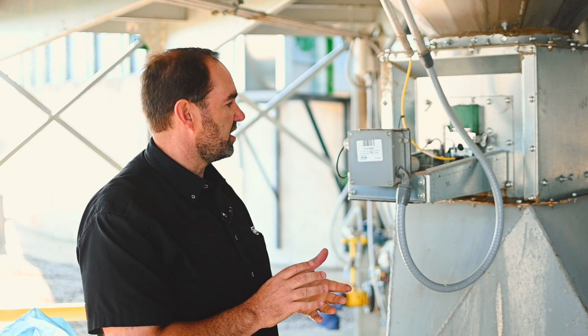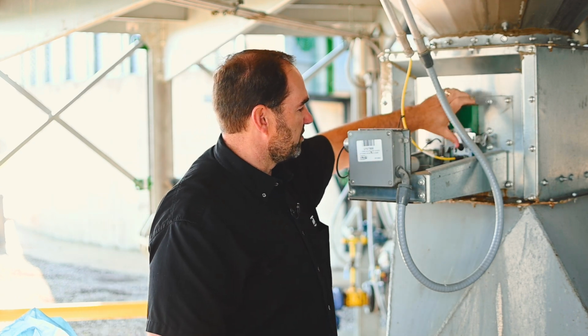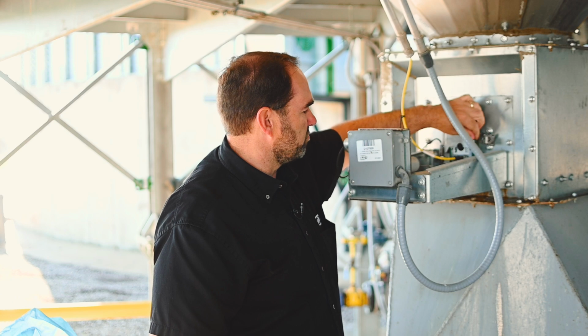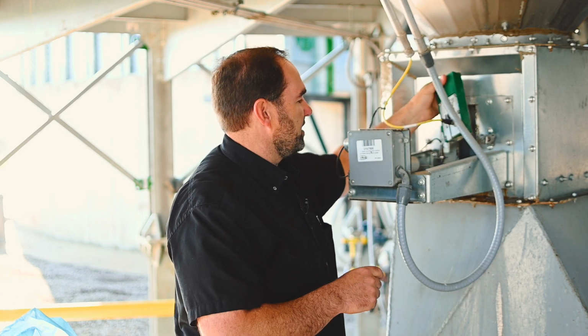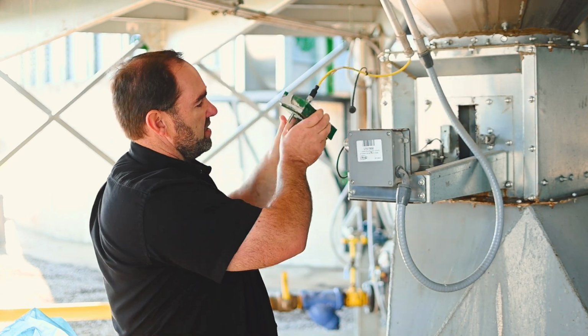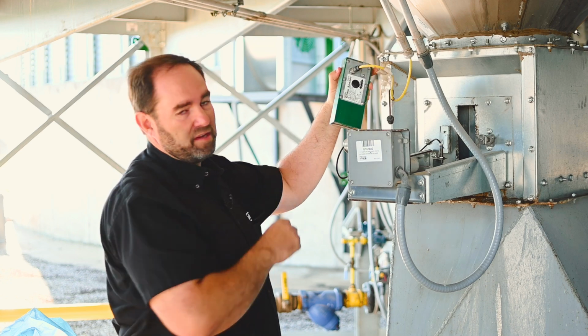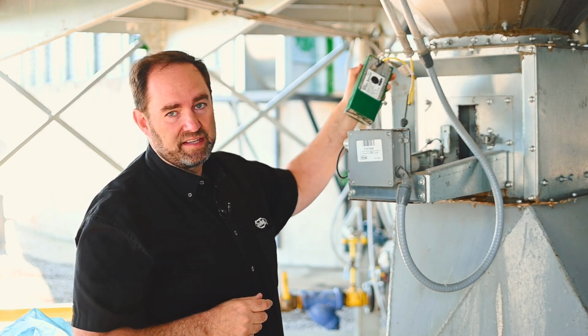So now we're at the discharge moisture sensor, and this is what we call a static moisture sensor. So let's take a look at how that works. The sensor itself is the green block here, and to get it out, you would remove the clasp, open it, and take it out. And in the off season, this just has a quick disconnect. So I do recommend not storing this on the dryer. It's best to take it inside in the off season.